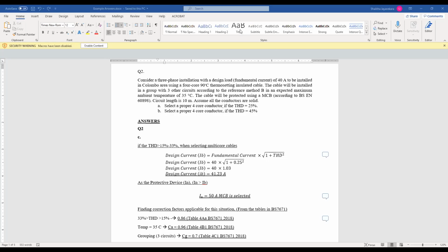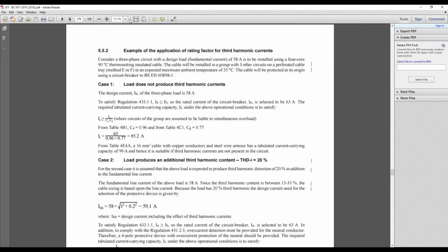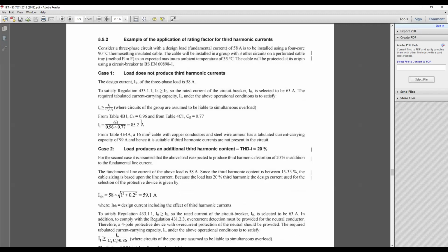This equation is directly taken from the BS 7671. I think this is explained on page 380. See, if you observe, here they have given an example of 20% THD, and your design current will be the fundamental times (1 + 0.2). 0.2 means 20%. So we are going to apply it as a per unit value. That means if it is 100%, this will be 1. If it is 50%, this will be 0.5. Now here it is 20%, so this is 0.2. This is how you are going to calculate your design current.